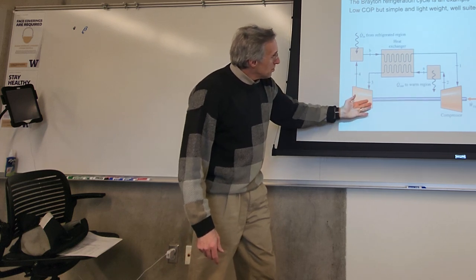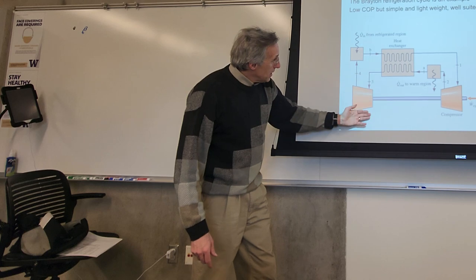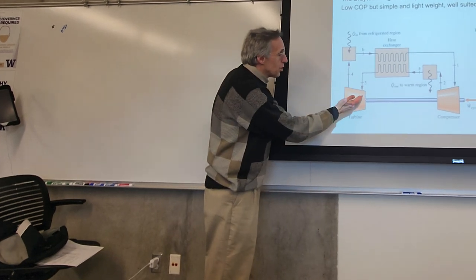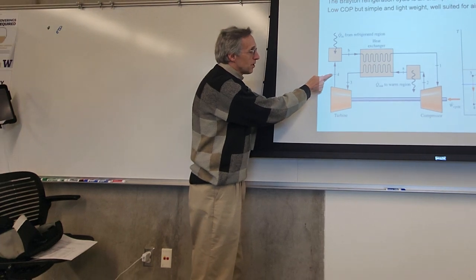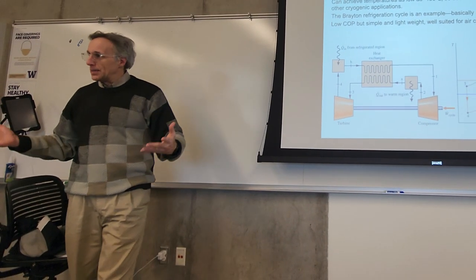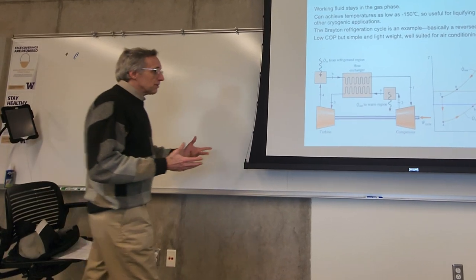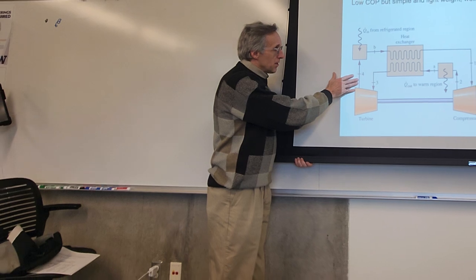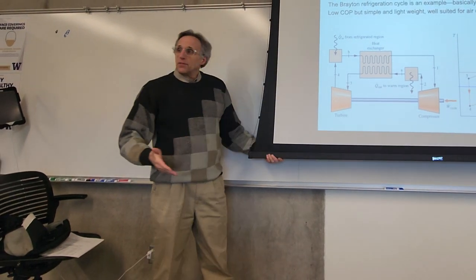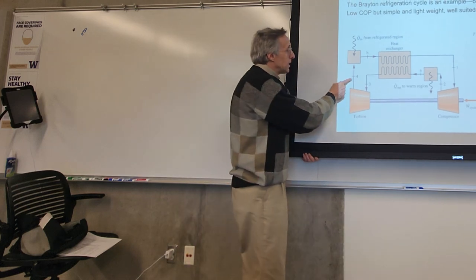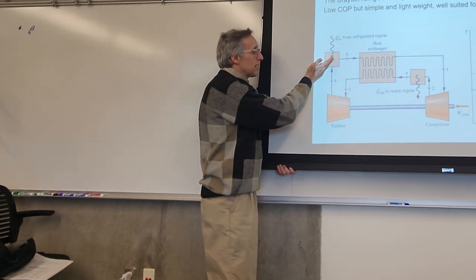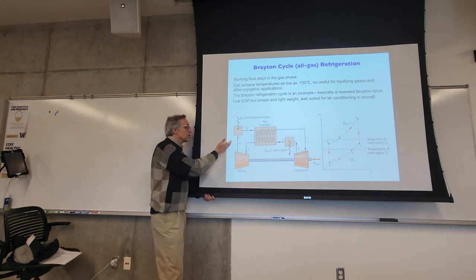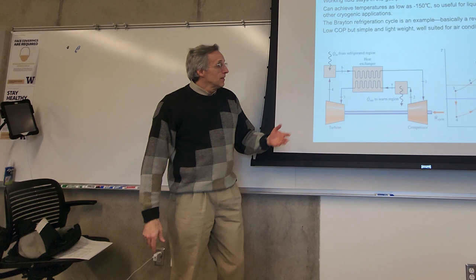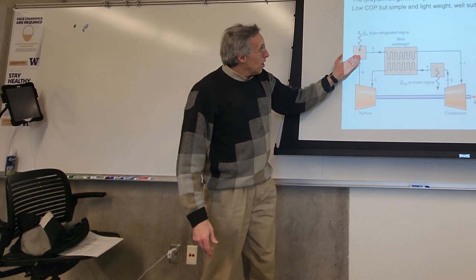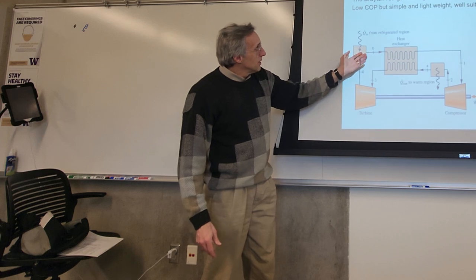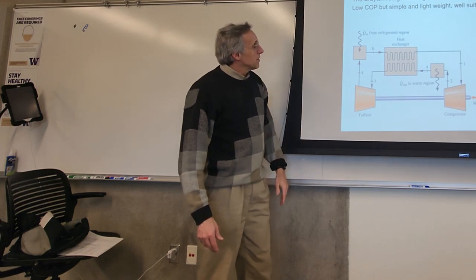And then you expand it in a turbine. And expanding it in the turbine pulls the temperature down. You run the turbine so that the output here is close to what you want the cabin, the inside pressure. So you want this around 14-15 psi coming off the turbine here. And then it goes into the cabin. And it's not changing phase, so this is not an evaporator, it's just a heat exchanger. And it has a fan that draws the cabin air across it. This is nice and chilly, nice and cold, and you get some nice cooling out of it.